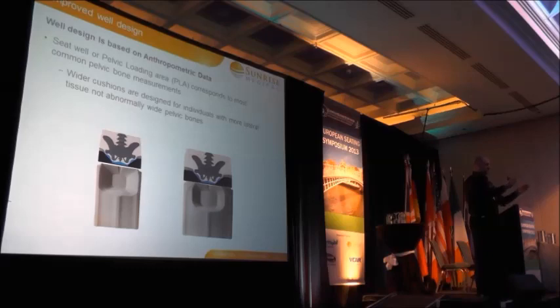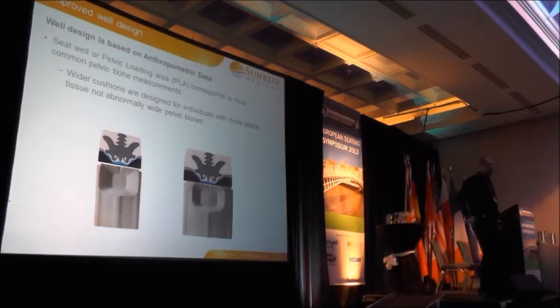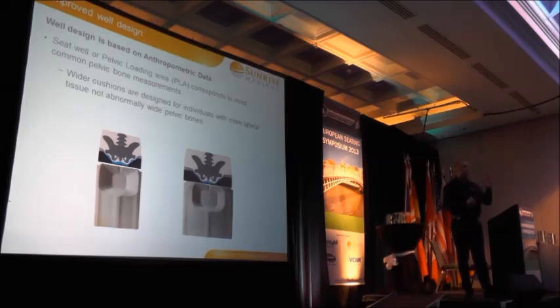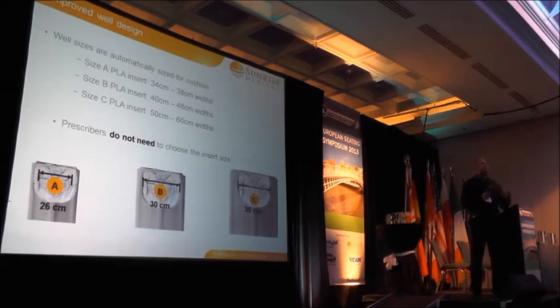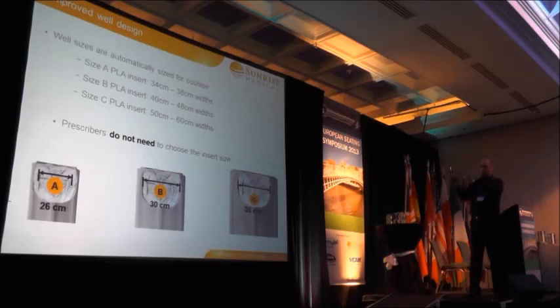Someone 26 inches wide will also share that same pelvic loading area; the growth is in the lateral tissue at the sides. In 5% of cases, it will be due to abnormal bone growth, and that's accepted. So with the Jay Balanced Cushion, there are three pelvic sizes — the pelvic loading areas — and they are automatically determined on the order form, meaning that in 95% of cases, that well size is going to work well for the client.